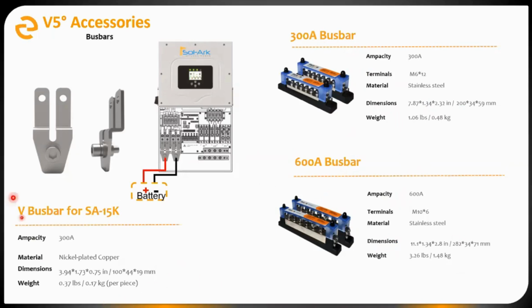The last thing to show is something we use much more frequently than these 2 bus bars: our V bus bars, specifically designed for the Sol-Ark 15K. As some of you know, the Sol-Ark 15K inverter has basically 2 positive and 2 negative battery terminals inside of it. What we like to do when it makes sense is use this V bus bar — one to join the 2 positives, another to join the 2 negatives. This lets you run a single set of higher gauge, heavier gauge cable from the battery bank to the inverter.